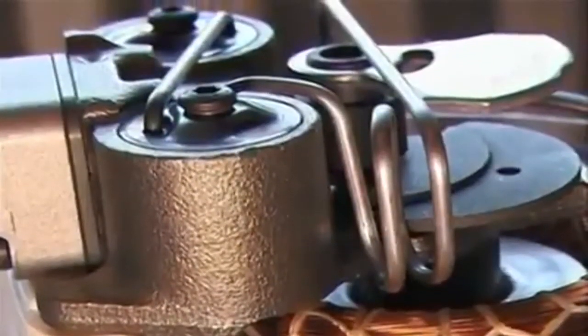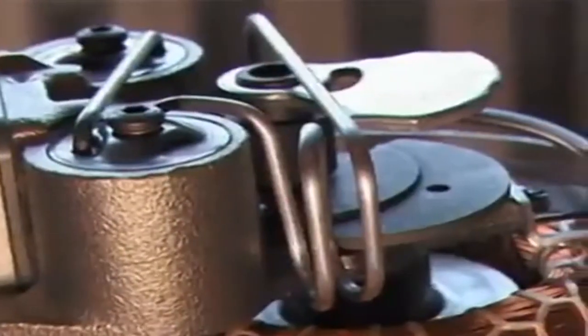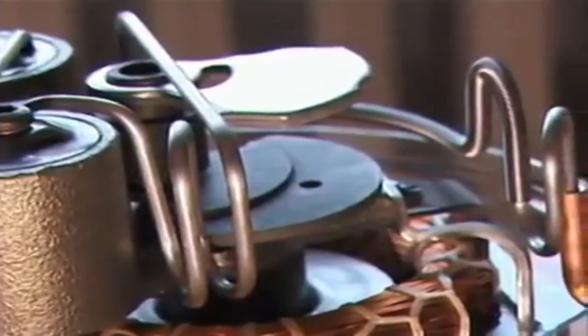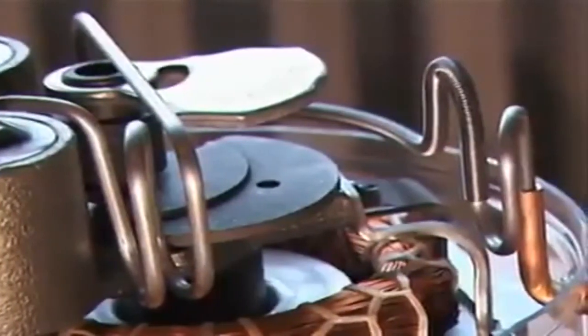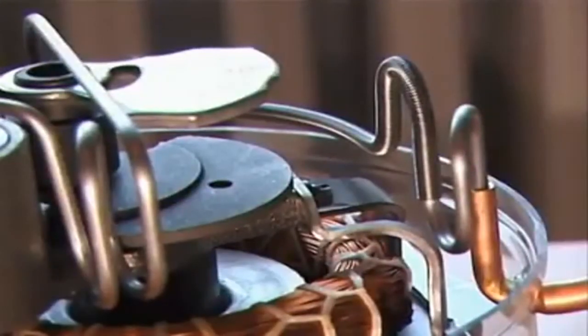This block has two discharge chambers. From these chambers, the compressed refrigerant passes through the discharge tube to the discharge connector of the compressor. The turns of the discharge tube increase the flexibility of the tube. They minimize the oscillations of the pump unit and prevent the tube from breaking during operation.